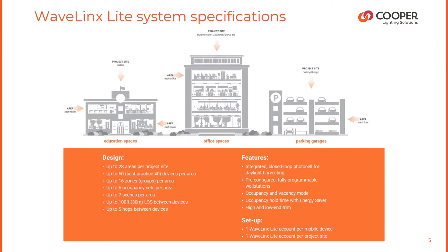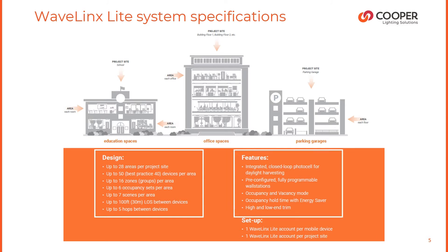In terms of features, there is an integrated closed loop photocell for daylight harvesting, and also occupancy detection through passive infrared. Our premise is based on speed of installation — a contractor can install a luminaire with occupancy and daylighting capability at the same time they install the basic lighting. Pre-configured fully programmable wall stations offer out-of-the-box functionality as soon as they join that area, and are fully programmable with the WaveLinx Lite app. Occupancy and vacancy modes are available, and high-end and low-end trim are also available in response to energy code requirements.